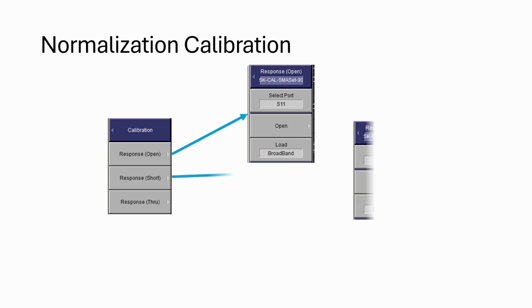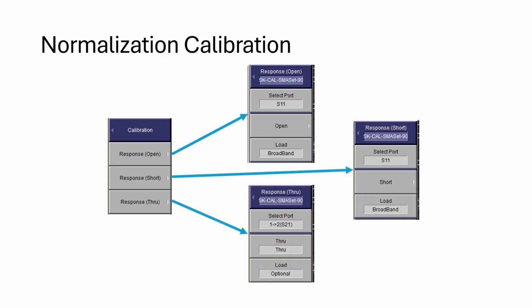Another one-port calibration option, mentioned here only for reference, is a normalization calibration. This allows the operator the freedom to limit the different standards to connect, then correct for limited response type. While this may act as a shortcut to save you some time, you will end up sacrificing on accuracy.